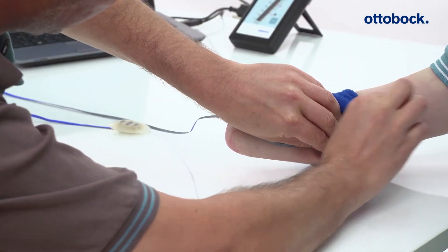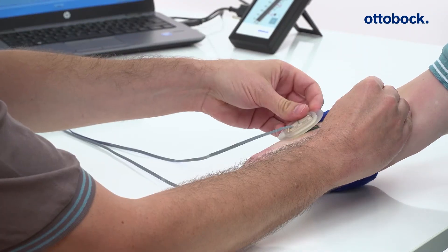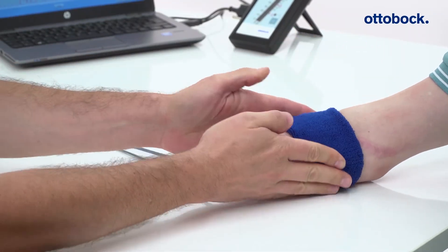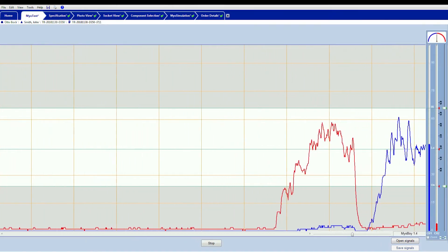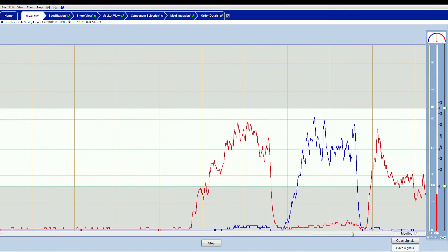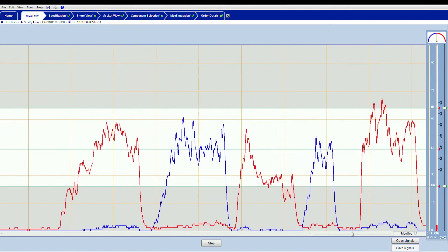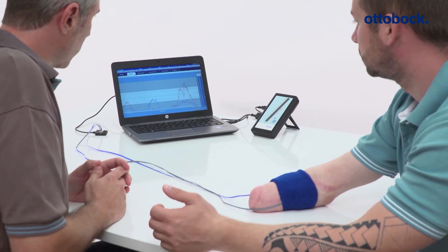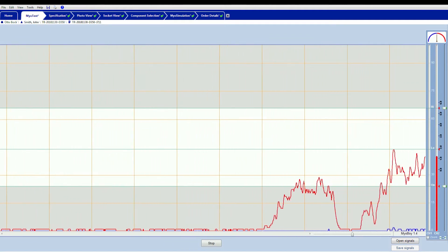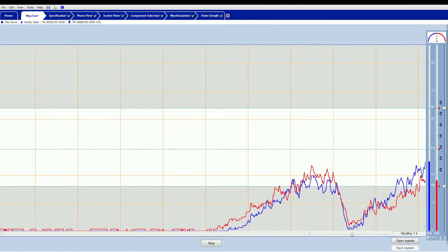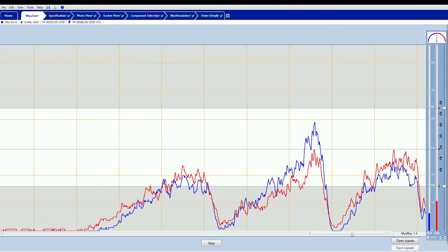Fix both electrodes on the marked positions with the electrode armband. For reliable prosthesis control, two well-separated MYO signals are required. Signal separation must therefore be tested with Paula software after determining the electrode positions. The aim is to generate two well-separated MYO signals when the user is contracting with different strengths. In the case of insufficient signal separation or overlapping signals, repeat the process for determining the electrode position.